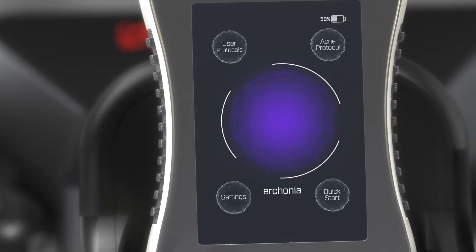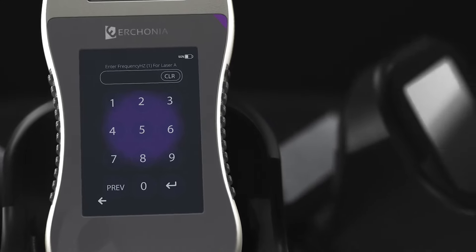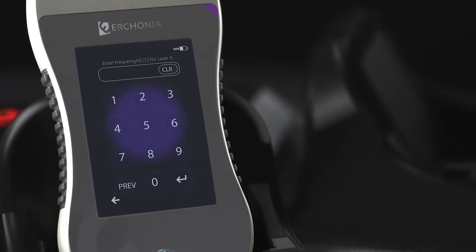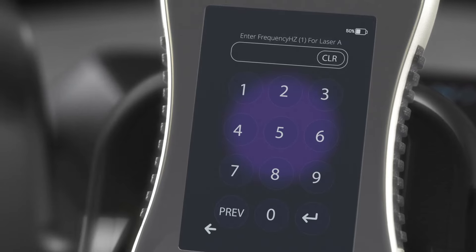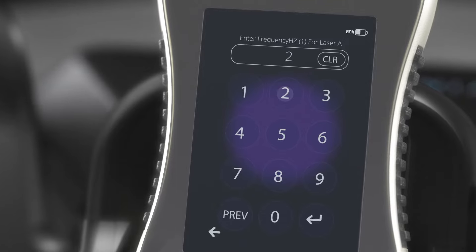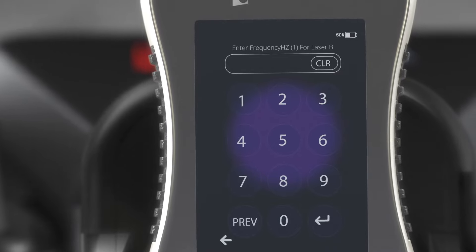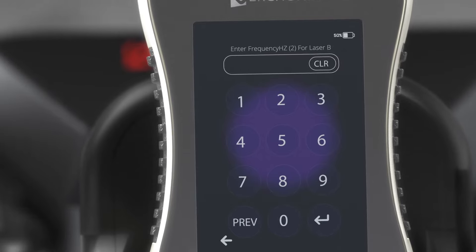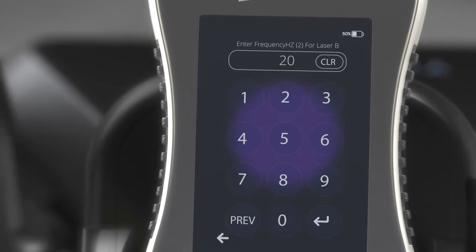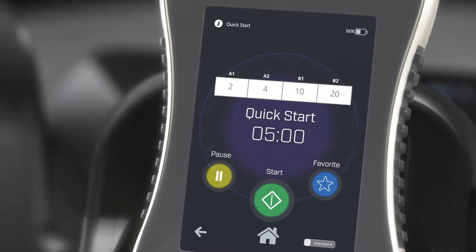Quick Start is for manually starting one-off protocols that will not be saved into the device. A Erchonia laser protocol consists of four frequency numbers, two per laser diode. The first screen will ask for frequency one for laser A — let's input two. Then it will ask for frequency two for laser A — let's input four. Then frequency one for laser B — let's do 10. Then frequency two for laser B — let's do 20. Next, it will ask for treatment time length — let's do five minutes. Hit Start and you can see our protocol in action.